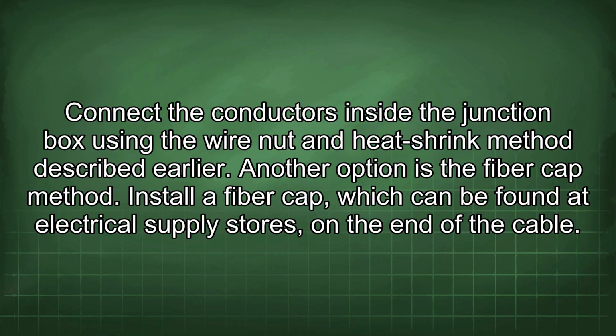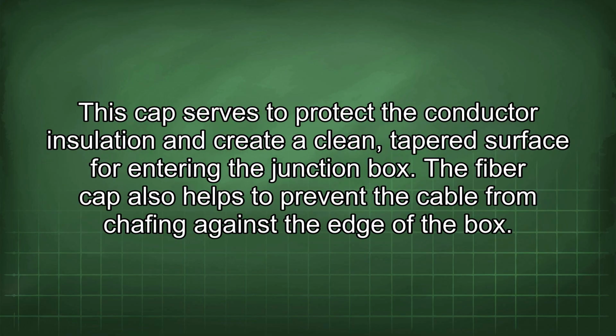Another option is the fiber cap method. Install a fiber cap, which can be found at electrical supply stores, on the end of the cable. This cap serves to protect the conductor insulation and create a clean, tapered surface for entering the junction box. The fiber cap also helps to prevent the cable from chafing against the edge of the box.